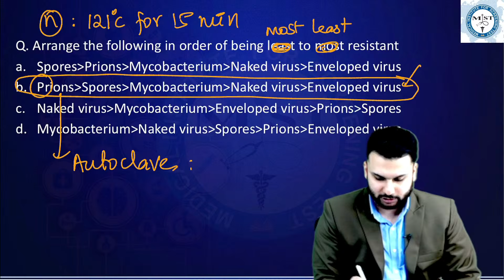Hot air oven, look at the name, it is hot. The temperature is very hot, it is 160 degrees, that too for 2 hours. So in the hot air oven the temperature is high, 160, and the duration is also high, 2 hours. Not every object we want to sterilize can survive this high temperature. So if a substance is not going to withstand that high temperature, what we do is bring down the temperature. And that is the purpose of the autoclave. Autoclave is used for those substances which cannot be sterilized by hot air oven.